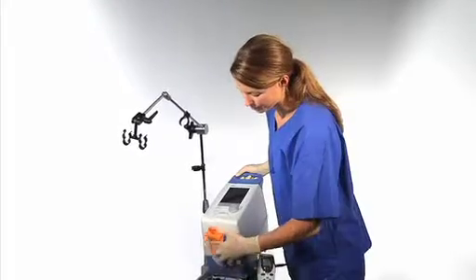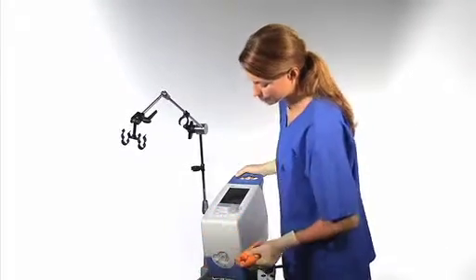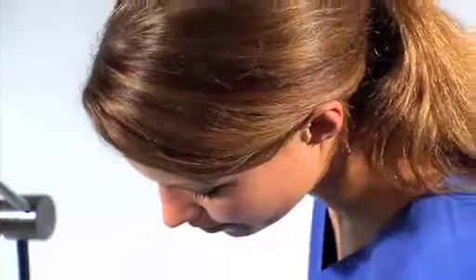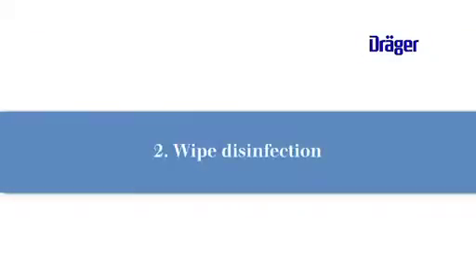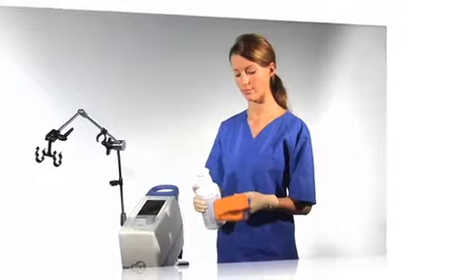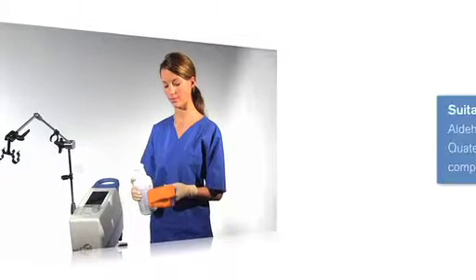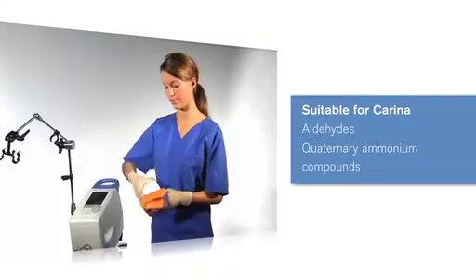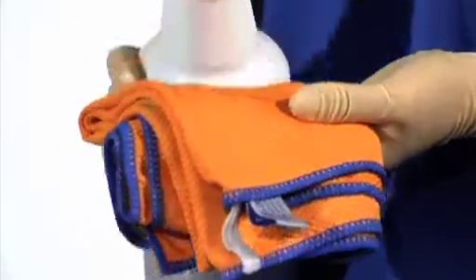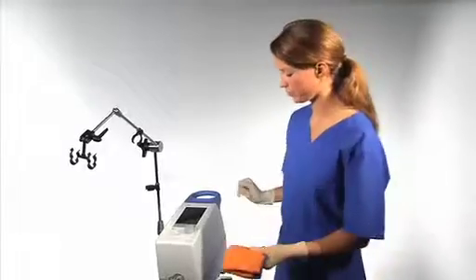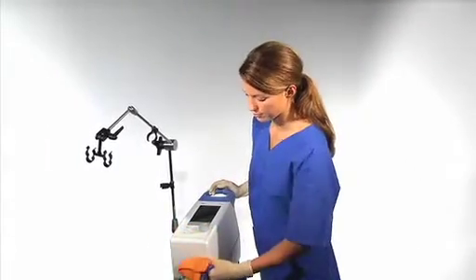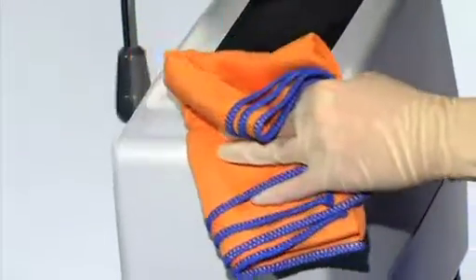Now wipe the surfaces with a clean, damp, lint-free cloth without using corrosive detergents. Wipe surfaces until they are free of all spots and dry them. Disinfectants based on these ingredients are suitable for Carina: aldehydes, quaternary ammonium compounds. Please note that the concentration, temperature and exposure times are different with every different disinfectant. If there are questions, please consult the individual manufacturer's instructions for use.